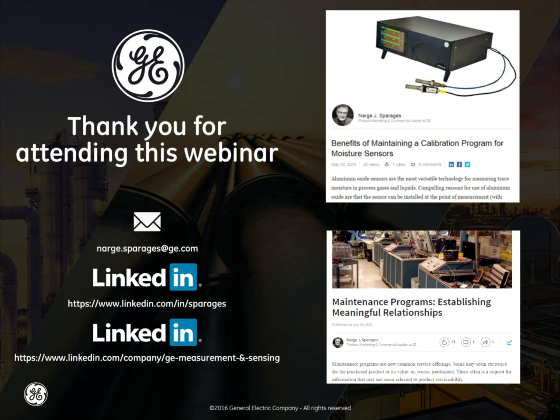For more strict applications like hydrocarbon gas, hydrocarbon liquids, our recommendation is 6 to 12 months. Typically a 12-month cycle is adequate for keeping the sensor healthy and keeping the measurement online. So this is the balance between keeping the measurement online and keeping the measurement healthy. We have another question. What is the shelf life for my aluminum oxide moisture sensor? Let me see how I can address that.